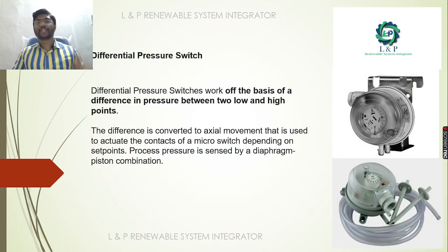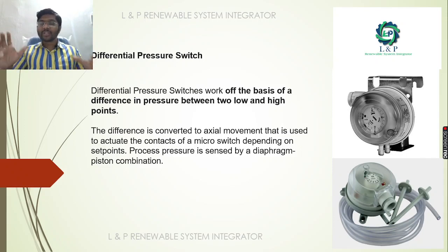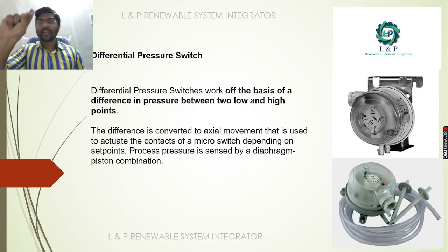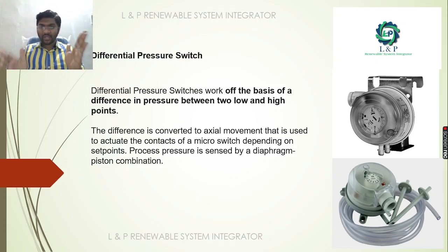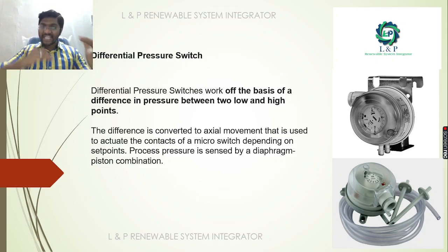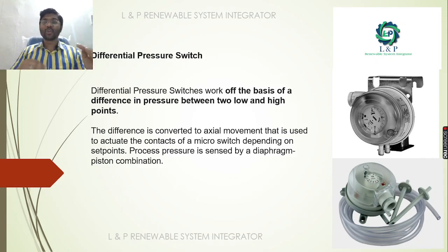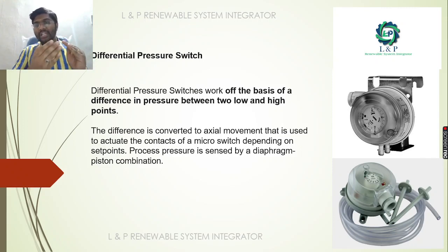A differential pressure switch works on the basis of the difference in pressure between two points. Normally, we create two points — one connected on the low pressure side and the other on the high pressure side — and we set a set point. If the pressure difference is greater than the set point, it acts as a switch. Normally it will be in the NC position, same like a relay. When the actual pressure exceeds the set point, the switch position changes from NC to NO, and the one already in NO changes to NC.